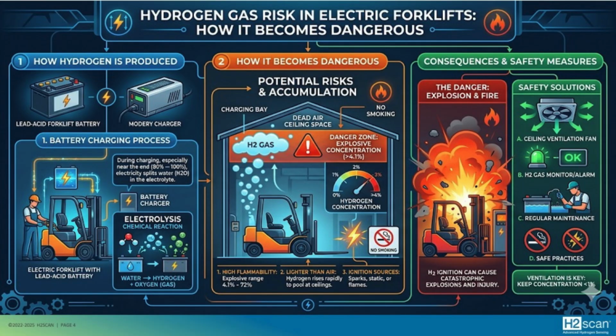Just an overview. I created this little AI graphic for us to show the process. Batteries are charging, and this could be charging directly from the forklift truck, or it could be charging from a multi-battery charging bay. Either way, the electrolysis happens inside of the battery, emits gas, and then of course we have this enclosed space that we have to monitor. Most of the time, again, per OSHA regulations and per fire code, you have to evacuate the air in that space. So you have safety fans that are running pretty much nonstop.